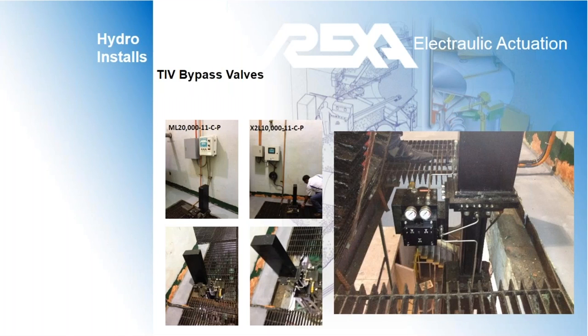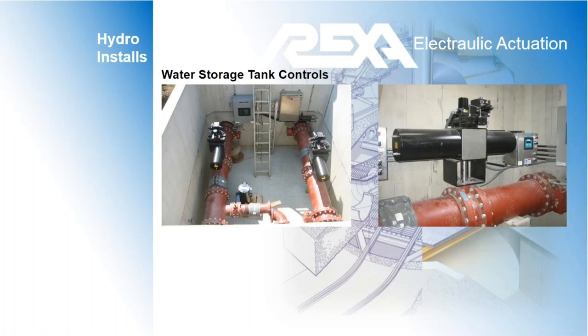And the Rexa operation is not limited to modulating control. Although that capability is there, it can also be used for on-off applications. In this case, it's used to operate turbine inlet bypass valves. These water storage tank controls have universal spring fail for a trip scenario. The trip function can either be clockwise or counterclockwise.